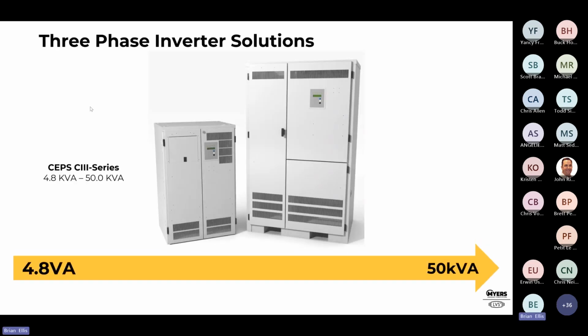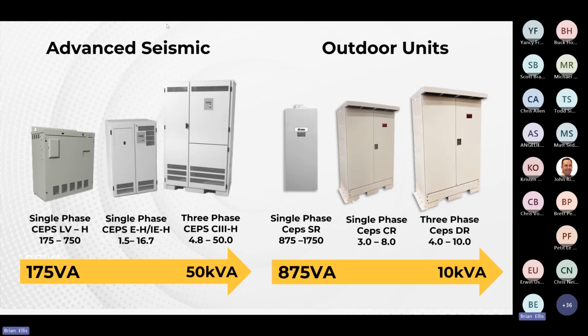For the three-phase solutions, we have the CEPS CIII, or what we also call the D series, and that is 4.8 kVA all the way up to 50 kVA. We have advanced seismic systems for certain parts of the country where that's important, as well as outdoor units. Whether you put this SR on a pole for a ball field, or you need a CR/DR single-phase or three-phase larger outdoor unit.